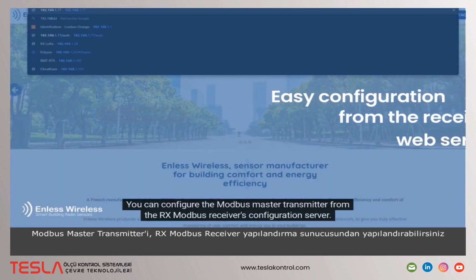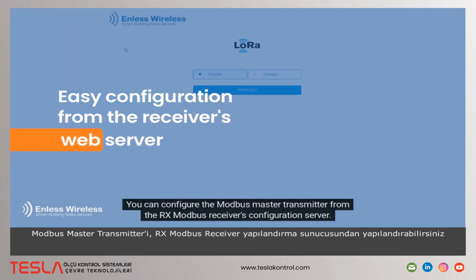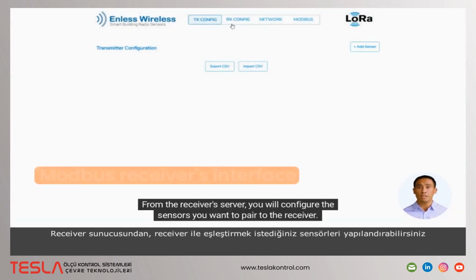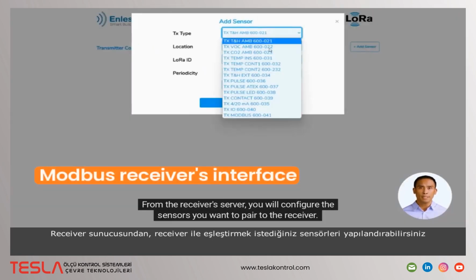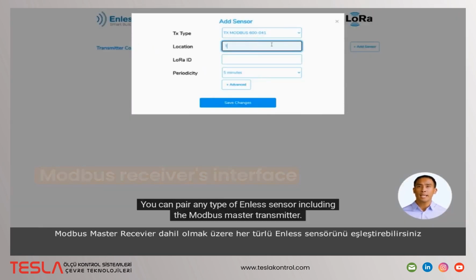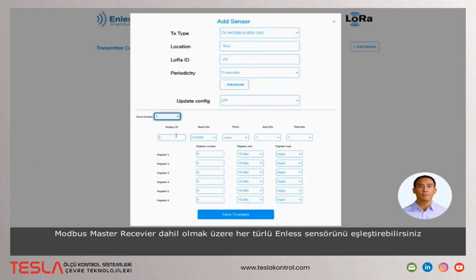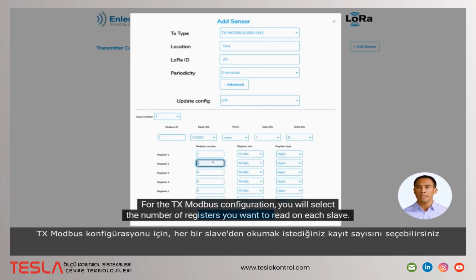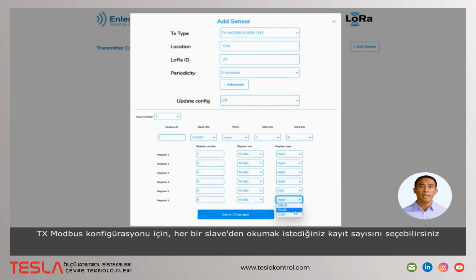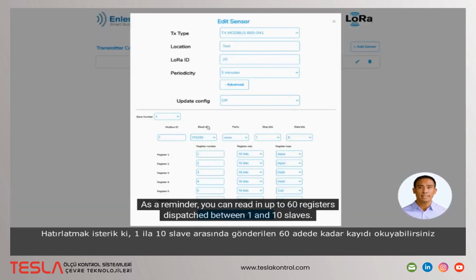You can configure the Modbus Master Transmitter from the RX Modbus Receiver's configuration server. From the receiver's server, you will configure the sensors you want to pair to the receiver. You can pair any type of Enless sensor, including the Modbus Master Transmitter. For the TX Modbus configuration, you will select the number of registers you want to read on each slave. As a reminder, you can read in up to 60 registers dispatched between 1 and 10 slaves.